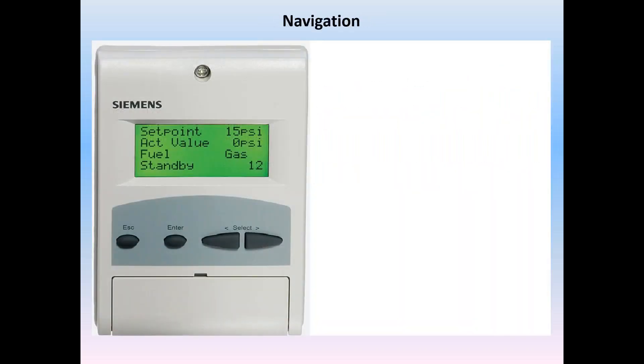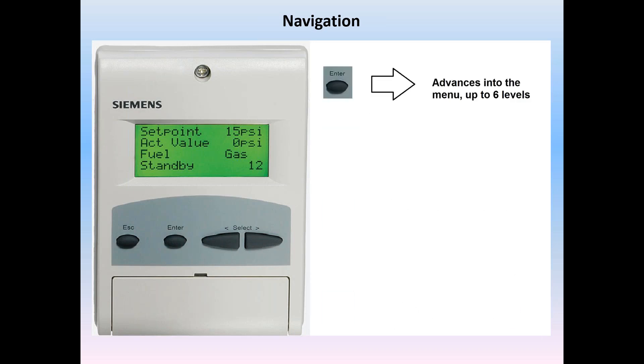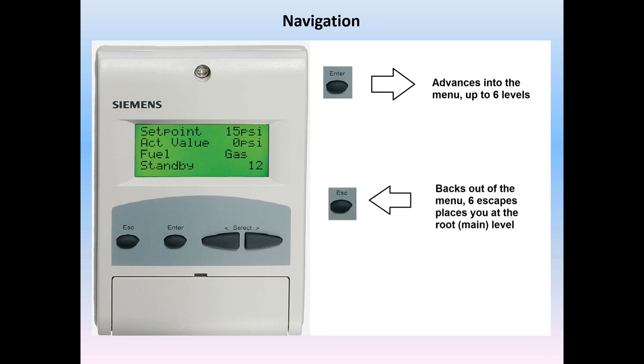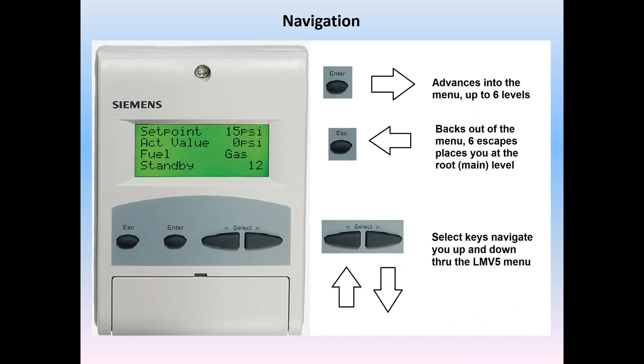Navigation. The AZL uses four keys to navigate the LMV5 system menu: Escape, enter, and the two select keys. The enter key drives you deeper into the menus and can go up to six levels deep. Escape key brings you back out. Up to six times will bring you back to the root main level. And finally, the two select keys move the menu up and down for navigation.